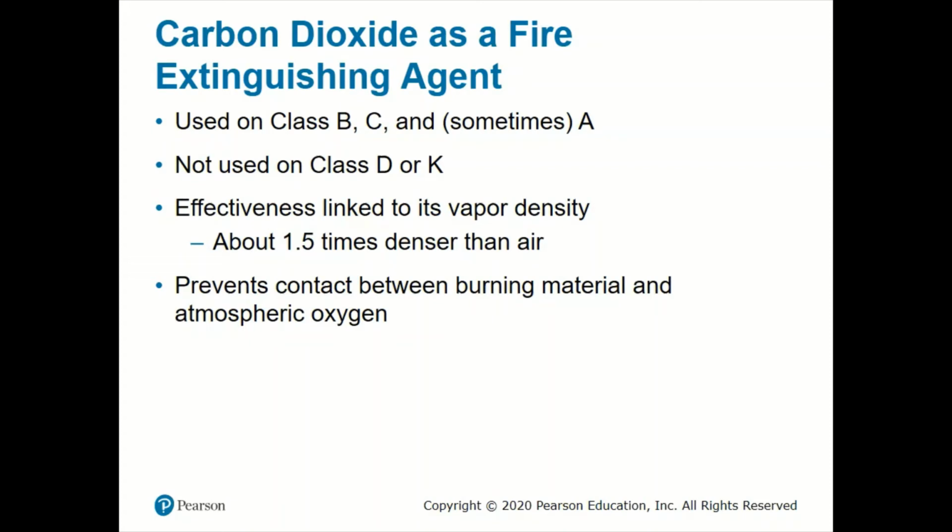First of all, because they are heavier than air, when we spray them out, it's going to go down and spread out in a downward fashion. And its primary purpose isn't for heat reduction like water was. It's for putting a barrier between the burning material and the oxygen in the air. Since it is more dense than oxygen, if you've got a layer of carbon dioxide around your fuel, it's a lot harder for the oxygen to get in there to burn it. And so that's where carbon dioxide is the most effective.